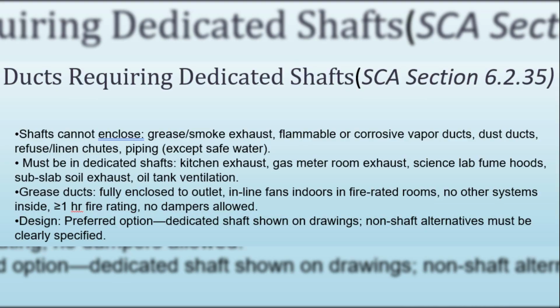For kitchen grease ducts specifically, the rules are strict. Any grease duct that passes through a ceiling, wall, or concealed space must be enclosed from the penetration point to its discharge outdoors. Inline fans that are not outdoors also need to be enclosed in fire-rated rooms with proper ventilation and cleaning access. Importantly, these enclosures can only contain the grease duct, no other pipes or wires. And fire dampers or smoke dampers cannot be installed inside grease ducts. As for fire safety, duct enclosures must match the fire rating of the assembly they penetrate, but never less than 1 hour. The only exception is when a grease duct penetrates a non-rated roof or ceiling.